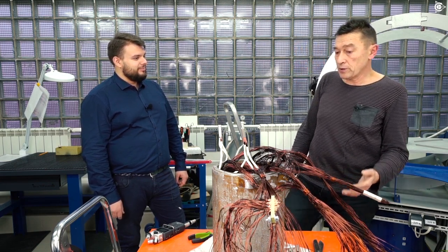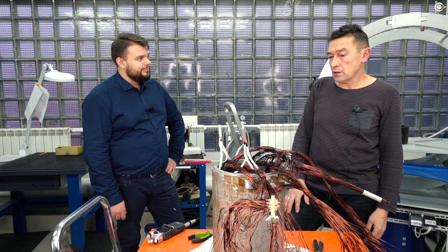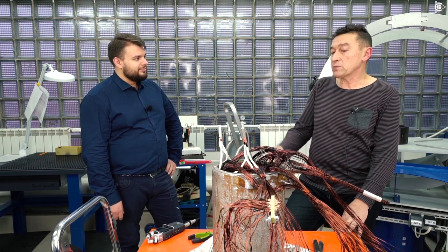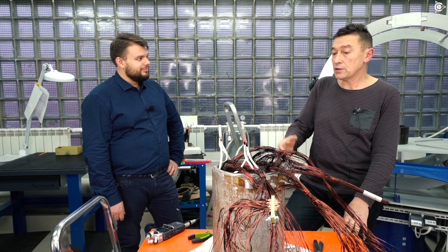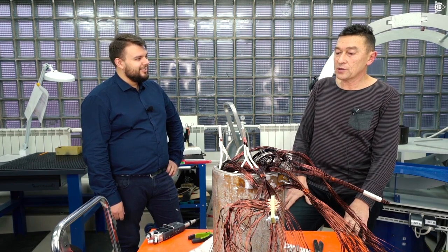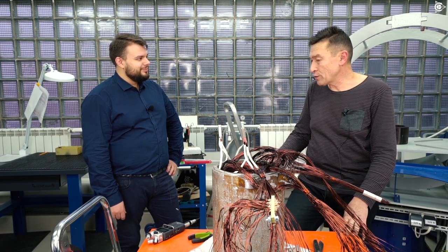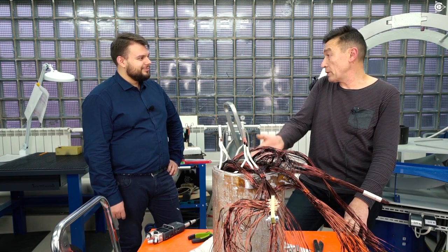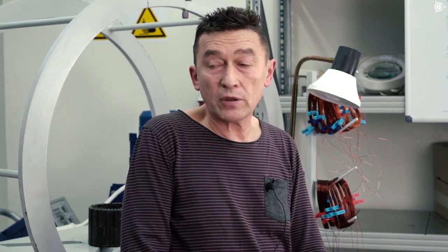It really happened, it was a compressor motor. A customer arrives, I say, now wait please until we check everything for you. And it doesn't rotate. Damn it, but it was necessary to give it back. So I disconnected and rewound it in one night. He comes in the morning and I say, everything is ready, you can take it. The customer says, come on, drop a ball. I say, I won't. The customer says, yes, throw a ball to make sure it works. I threw it. The customer says, it's not rotating again. I say, well, it doesn't rotate, but what can I do? Everything is correct, I couldn't have made a mistake here. And you have to figure it out yourself why it doesn't rotate.